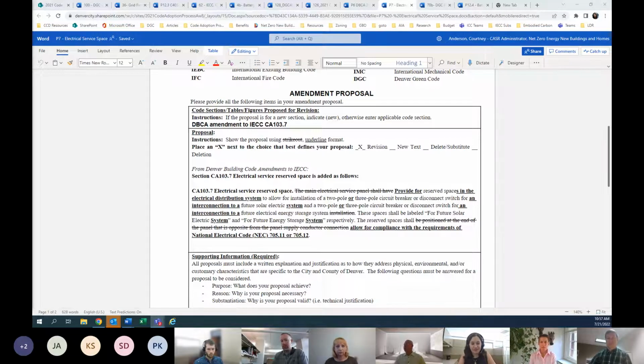Okay, the next one regards provisions for interconnection to PV systems and to energy storage systems. The language in the proposal is written so that interconnection can only happen in the main panel opposite the main device in the panel. Well, the National Electrical Code addresses the issue of interconnection of PV systems and energy storage systems that allows for other provisions besides that one. And I think we should follow what the NEC, the National Electrical Code, allows for how systems are interconnected.